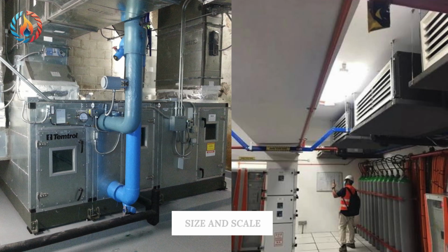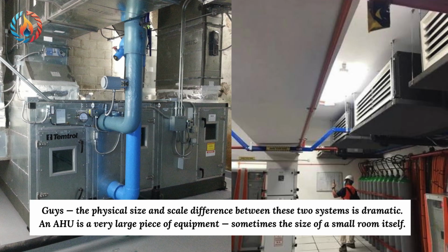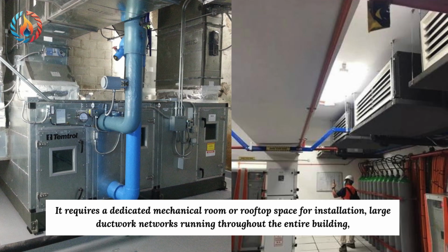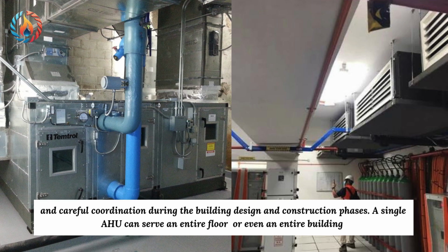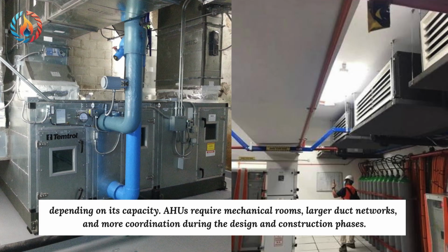Size and scale. Guys, the physical size and scale difference between these two systems is dramatic. An AHU is a very large piece of equipment, sometimes the size of a small room itself. It requires a dedicated mechanical room or rooftop space for installation, large ductwork networks running throughout the entire building, and careful coordination during the building design and construction phases. A single AHU can serve an entire floor, or even an entire building, depending on its capacity. AHUs require mechanical rooms, larger duct networks, and more coordination during the design and construction phases.